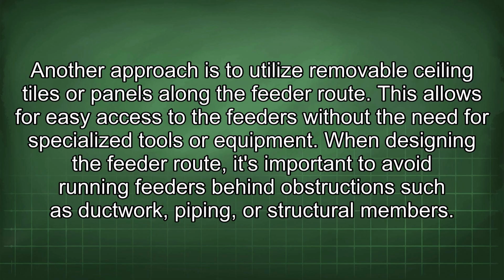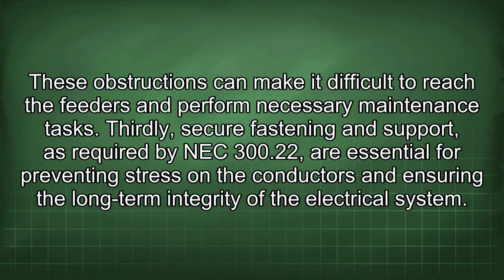Another approach is to utilize removable ceiling tiles or panels along the feeder route. This allows for easy access to the feeders without the need for specialized tools or equipment. When designing the feeder route, it's important to avoid running feeders behind obstructions such as ductwork, piping, or structural members. These obstructions can make it difficult to reach the feeders and perform necessary maintenance tasks.